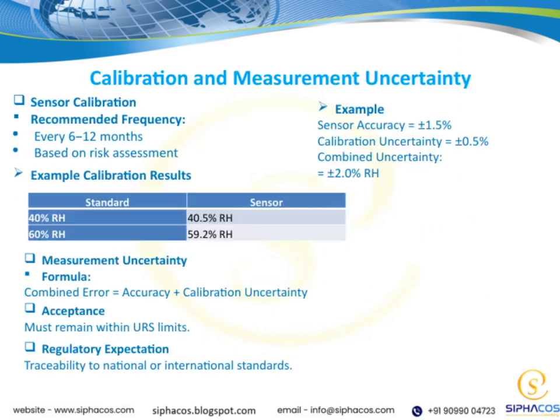Let's break down how we handle uncertainty in sensor measurements. We start with the sensor's accuracy, which might be plus or minus 1.5%. Then, we add calibration uncertainty, about 0.5%. When combined, that gives us a total uncertainty around 2% relative humidity. We use a simple formula: combined error equals accuracy plus calibration uncertainty. The key is that this combined uncertainty must stay within the user requirement specifications. Regulators expect us to trace everything back to national or international standards. Calibration is recommended every 6 to 12 months, depending on risk. This example shows how close the sensor readings are to the standards.